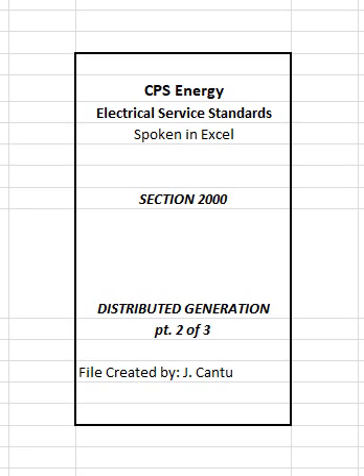1. Load side interconnections shall be made on the load side of the customer's main service panel. A main breaker is required and shall be used in the bus ampere rating calculation to ensure the bus rating is not exceeded. Interconnections for residential installations shall be made at exterior panels. 2. Line-side interconnections shall be made in a junction box or auxiliary gutter ahead of the service disconnecting means. Junction box shall be suitable for the conditions, provided with locking provisions, and be sized as per the NEC but not be less than 12 inches by 12 inches. Note 1. Conductors from junction box to PV AC disconnect shall be treated as service entrance conductors and shall be as short as possible; in no case shall the distance exceed 10 feet.